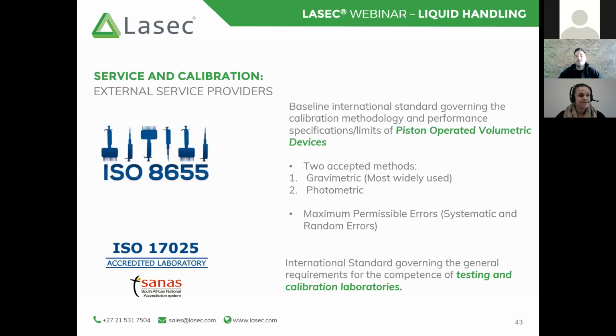All right, so there are two types of calibrations or standards that most people calibrate their pipettes to. The first one is the ISO 8655 standard. This is the baseline international standard, which really governs how to go about calibrating piston-operated volumetric apparatuses, which encompasses pipettes. It also encompasses bottle top dispensers, for example. So anything that's measuring volume that works with a piston is governed by ISO 8655. With this being the baseline, this is how all calibrations are to be carried out.